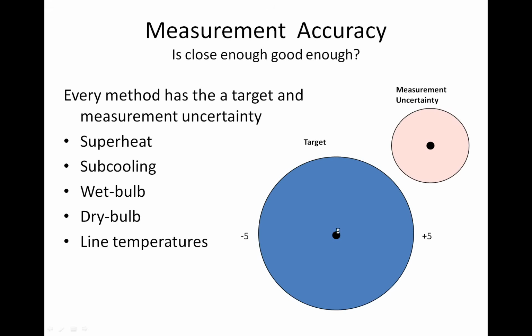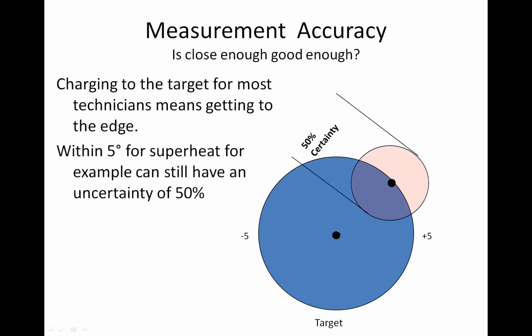But here's where we get into a problem. A lot of technicians, when they talk about hitting the target, that means charging the target to the edge. In other words, if we're required 15 degrees of superheat, and a technician gets to within 20 degrees of superheat, he goes, okay, well, perfect, right? I'm right at the edge. I have plus or minus 5, and I'm at 20, and okay, so I'm good. I'm within 5 degrees.